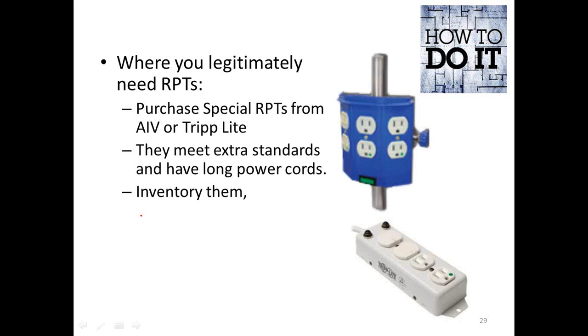Here's a key thing. Once you put an RPT in place, and you will have to buy enough of these to go out and replace any multiple outlet strips being used around patient care equipment, you've got to do a couple things when you put them in service. Number one, you have to inventory them. Remember, the rule says you have to have an ongoing maintenance program, and the only way to do that is to inventory them and treat them like any other piece of patient care equipment. I've long maintained that a multiple outlet strip, or RPT, is nothing more than a very simple piece of medical equipment. It has a cord, a male plug, several female receptacles, and maybe a circuit breaker. Other than that, it's a very simple item. Inventory it, surveil it, look after it, test it, document it, and you're set.